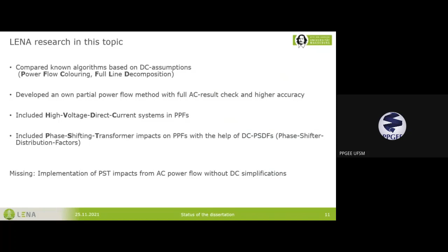The general idea is: if you have a phase-shifting transformer between two nodes in the grid, you can neglect the transformer itself and instead represent it by two current sources at the two nodes it connects. You have the overall power flow over this line, superposed by a current whose source is the phase-shifting transformer itself. Due to these two current sources, you get the same effect as before, and can then superpose all the currents of the system with the current from the phase-shifting transformer.